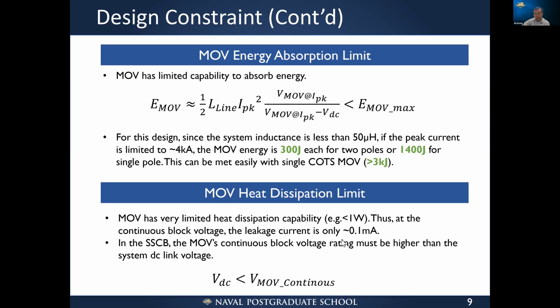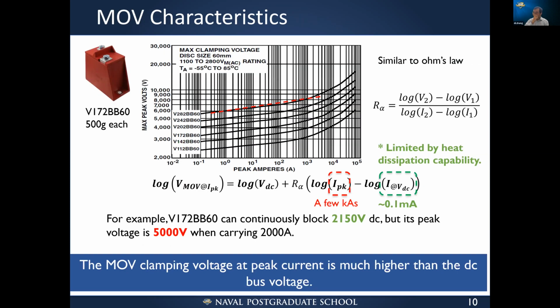So in the solid-state circuit breakers, the MOV's continuous blocking voltage rating, which you can find from the MOV's datasheet, must be higher than the system DC link voltage. VDC must be less than the VMOV continuous voltage. So as you can see, most of the design constraints are around the MOV. If we can find an MOV, for example, that can block 2 kilovolts continuously and also clamp the voltage fairly low, like 2.5 kilovolts at 1,000s of amps, the job is done. It will be easy.